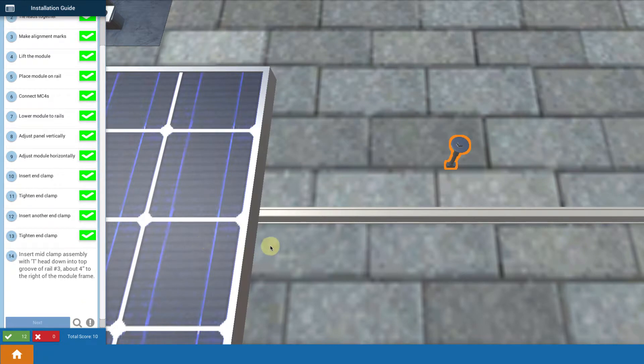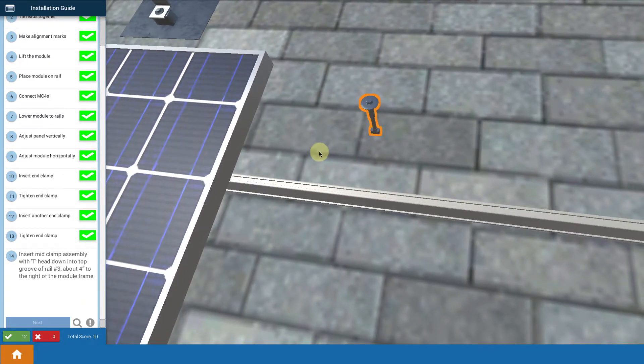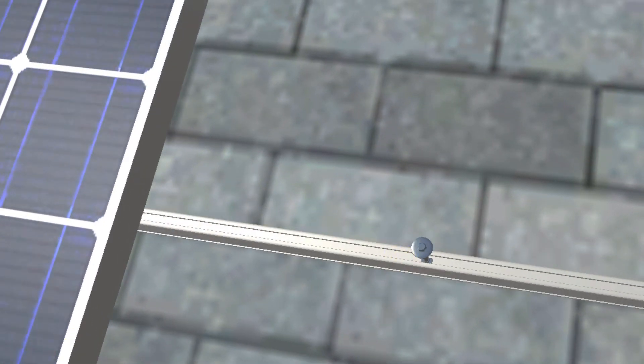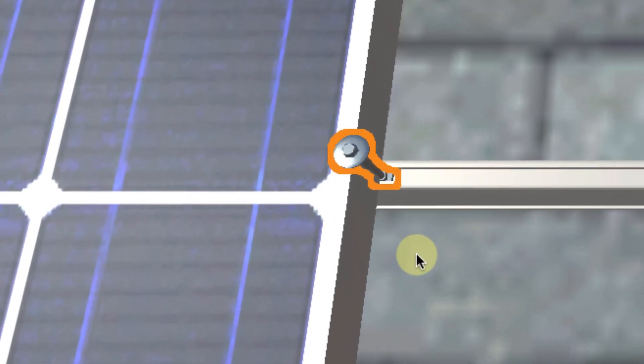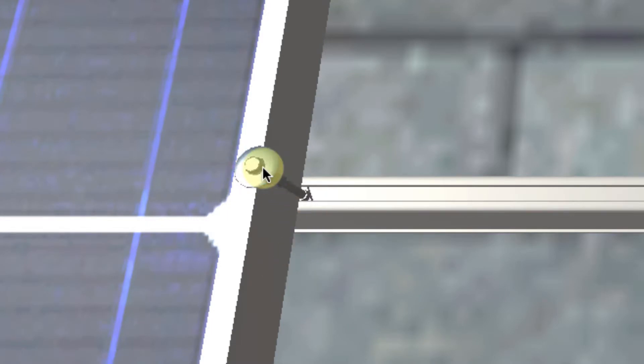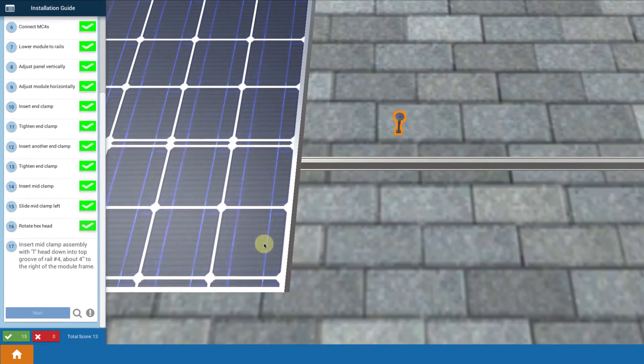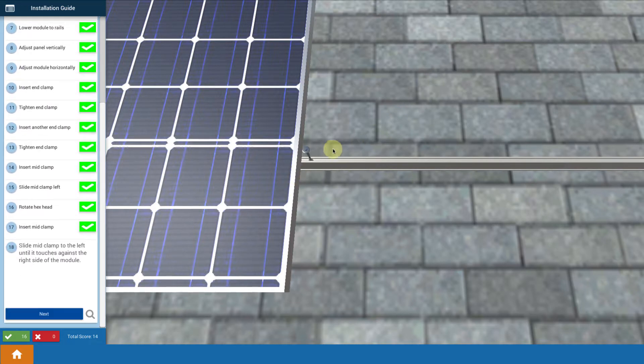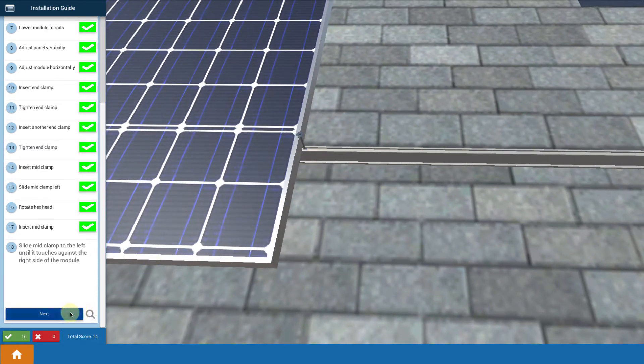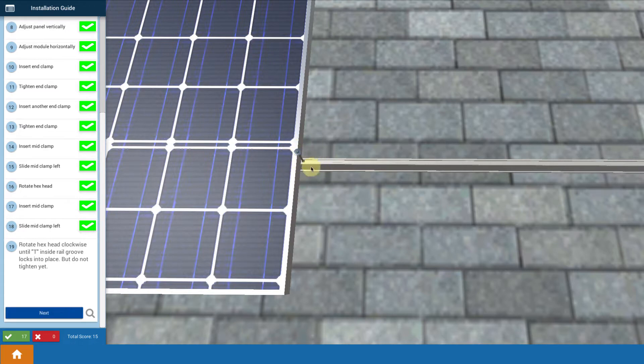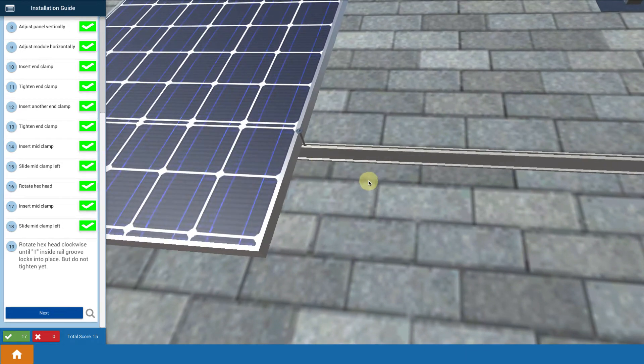Now on the other side, you use a probably a slightly different one. This one's more skinny. So this happens to be a particular choice of mounting system again with an inverted bolt. And you're going to touch on it to slip it into the rail system. Then you're going to slide it over until it touches the side of the module. That's how we're going to connect module to module. And then one more thing here. We're going to zoom in a bit here just to see. But the idea is that you want to rotate this guy. I'm going to touch it and you're going to rotate that bottom bolt head so it locks itself into the vertical groove that's in the top of the rail. Same thing down below. You're going to click on it to put it into the rail system. Then you're going to slide it on over until it touches flush with the module. And then you're going to rotate it. And we rotated that head inside so it locks itself in, basically holds itself up, waits for us to install the next module.